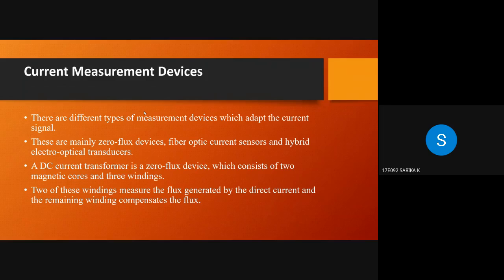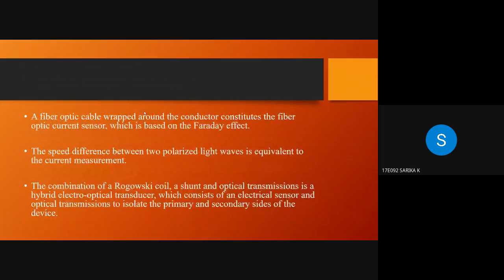First, zero flux devices. A DC current transformer is a zero flux device which consists of two magnetic cores and three windings. Two of these windings measure the flux generated by the direct current, and the remaining winding compensates the flux. A fiber optic cable wrapped around the conductor constitutes the fiber optic current sensor, which is based on the Faraday effect. The speed difference between two polarized light waves is equivalent to the current measurement.